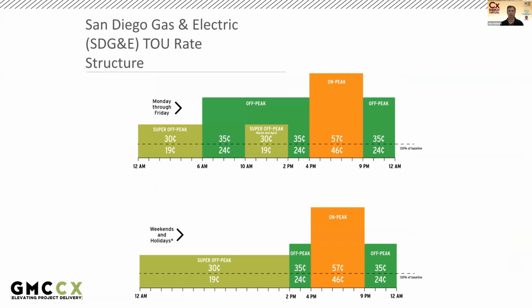So one of the main purposes of the microgrid is to save money. Obviously, there must be some payback. The way Sharp is able to reduce utility costs is to use the local utility, which is SDG&E here in San Diego, the rate structure to its advantage. SDG&E has 3 different rates depending on time of day, also known as TOU or time of use. Also different rate structures for the day of the week and the amount of usage. They have rates for on-peak, off-peak, and super off-peak.